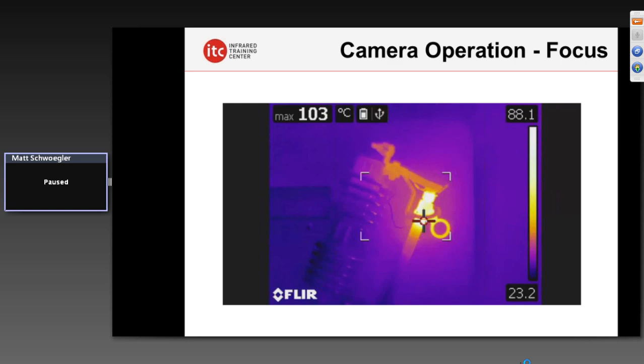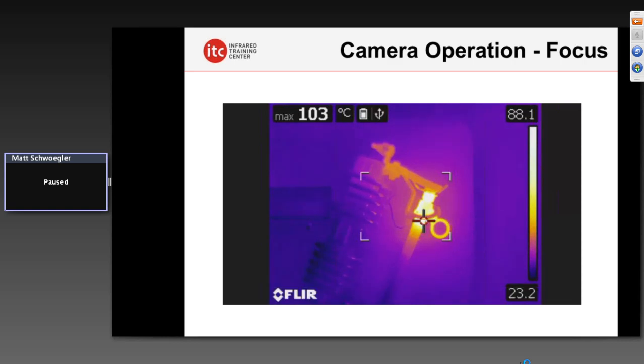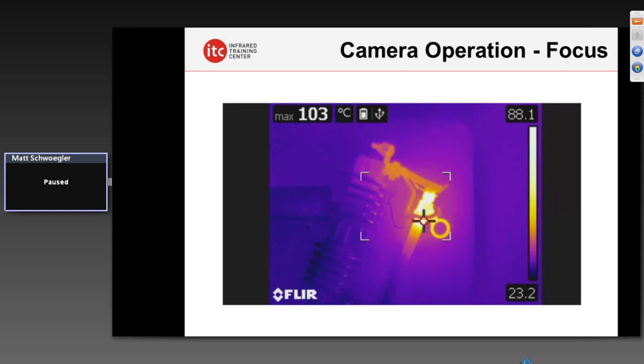For example, knowing how to properly focus is absolutely critical — not only to resolve detail on the surface of an object, but also for temperature measurement. This was actually taken in our lab in our Nashua, New Hampshire training facility. This is a cutout you might see on top of a telephone pole. We have a spot temperature on the surface showing us the maximum temperature of about 103 degrees Celsius — about 215 Fahrenheit or so. If you were to see this in real life, this would certainly be a problem you would report.